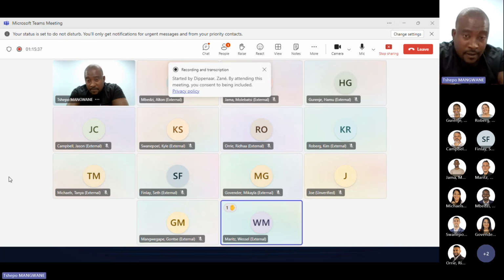Okay. And then the other question on the hybrid: can you mix and match the different sizes, like a 15 with a 25? No, unfortunately not, not on the hybrid side. But on the grid tie side, you can mix different sizes. 50, 33CX and 125 in parallel, yes, you can do, but in that case you will have to use the Logger1000 and COM100E communication module. On the hybrid side, we don't use the COM100E. We use the WiNet-S standard.